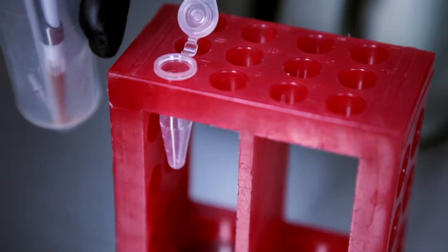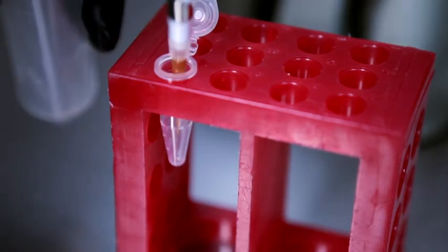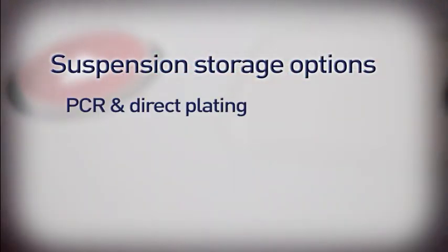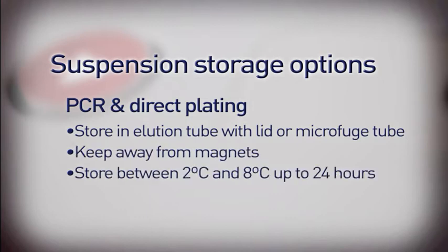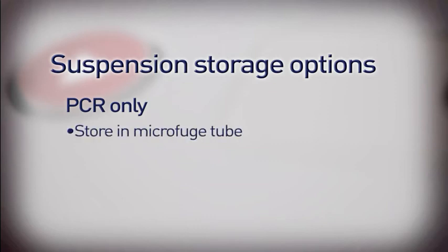If you need to store the bead suspension for later testing, you have two options. For PCR and direct plating, store the bead suspension in the elution tube with the lid or in a microfuge tube. Keep it away from magnets. Store it at a temperature between 2 and 8 degrees Celsius for up to 24 hours. If you prefer to use PCR only, transfer the bead suspension to a microfuge tube and store in a negative 20 degrees Celsius freezer for up to a month.